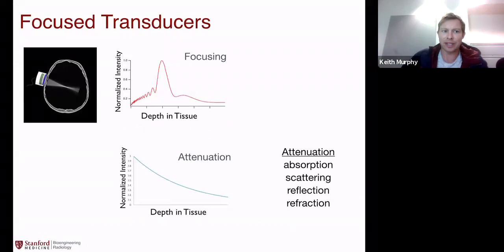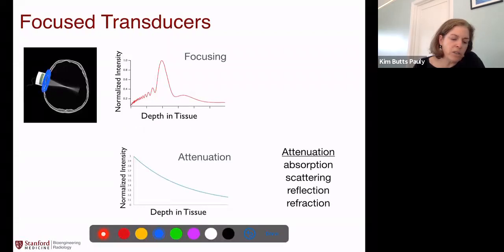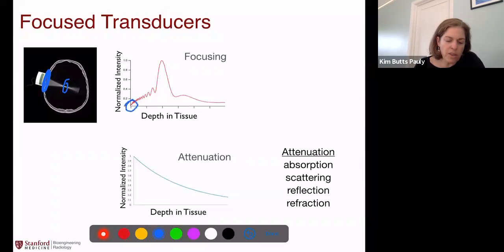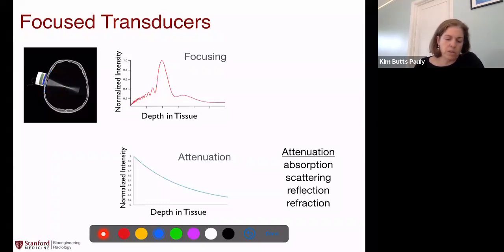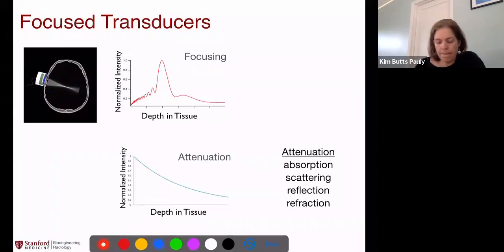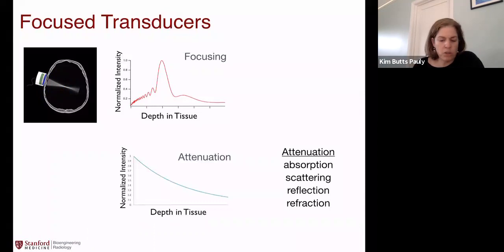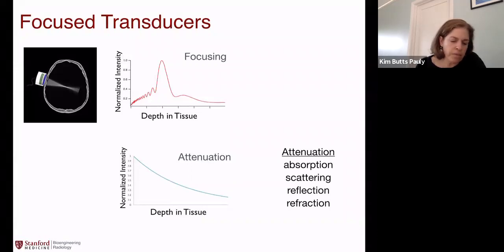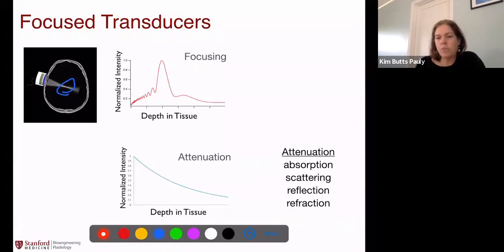Can you tell us about the term focal gain really quickly? There's a certain pressure that comes off the face of the transducer and a certain pressure at the focus. The gain is the ratio of one versus the other. You can see here the pressure coming off the transducer is very low, normalized to that value, but there's clearly very high gain with this focusing. We'll give you some equations for the gain and talk more about focal spot size — you could measure it from a picture like this, looking at the width and length at the minus 3 dB or minus 6 dB curves.